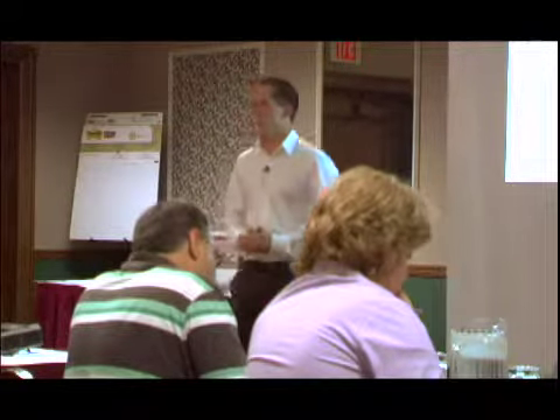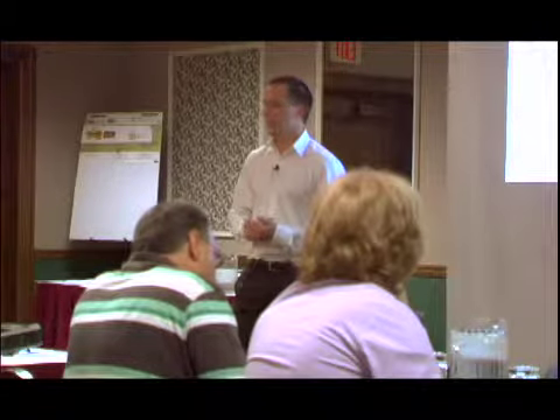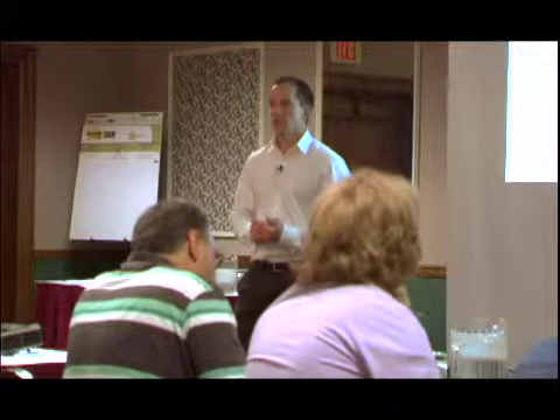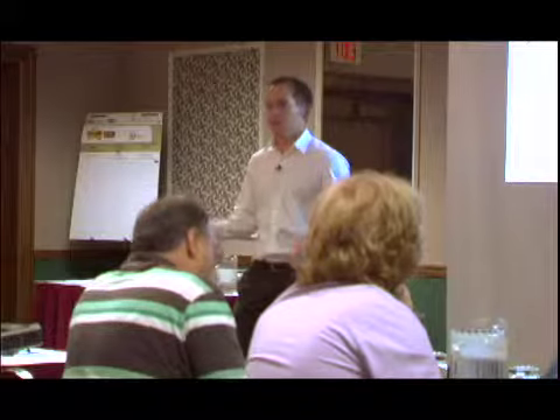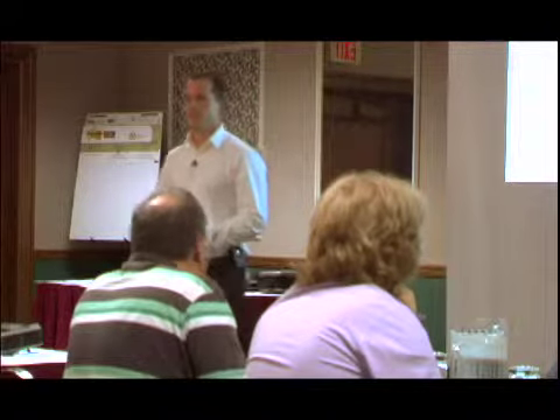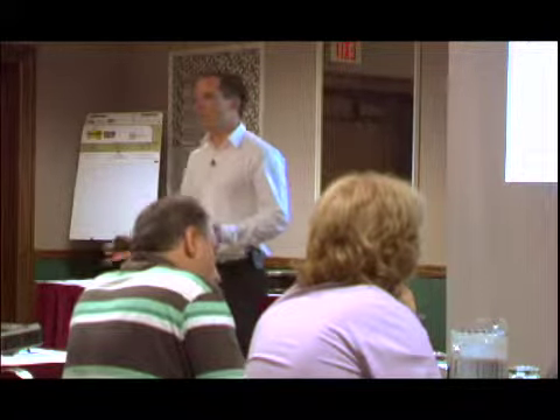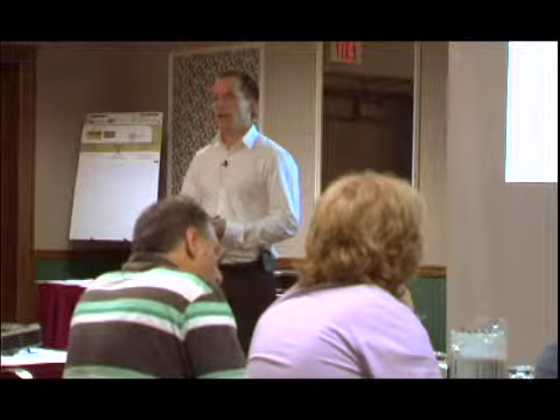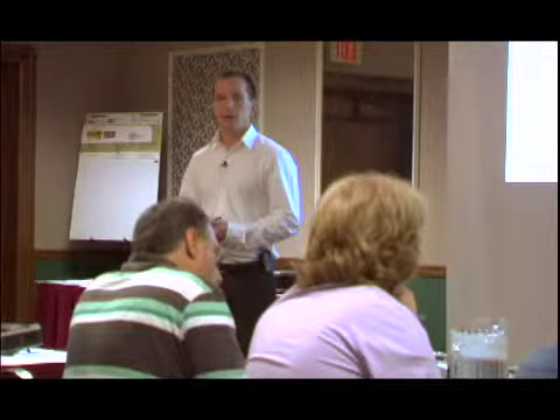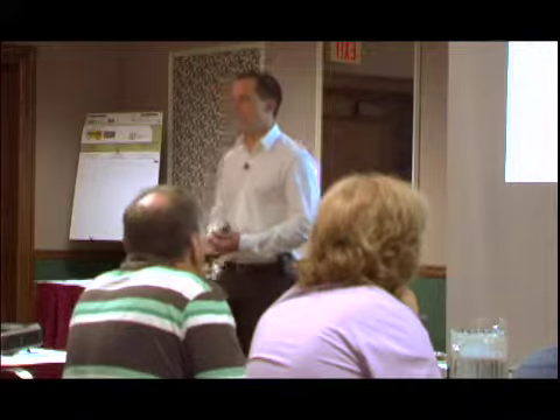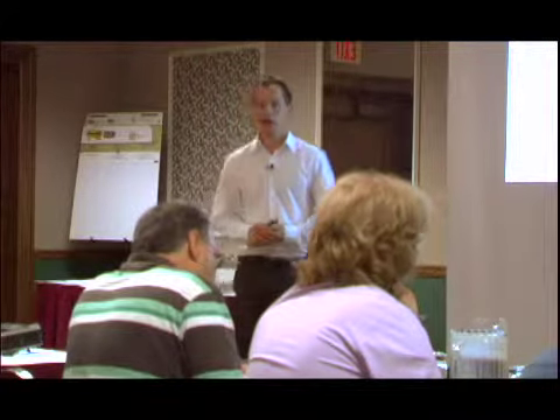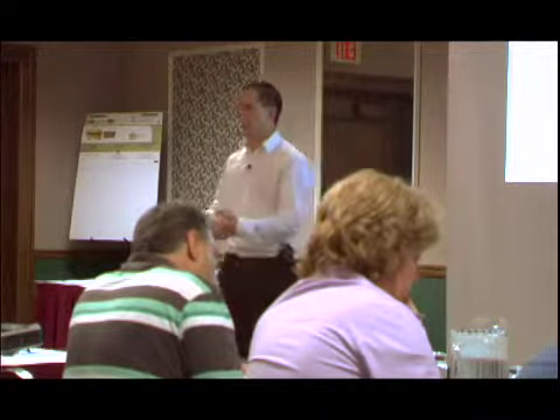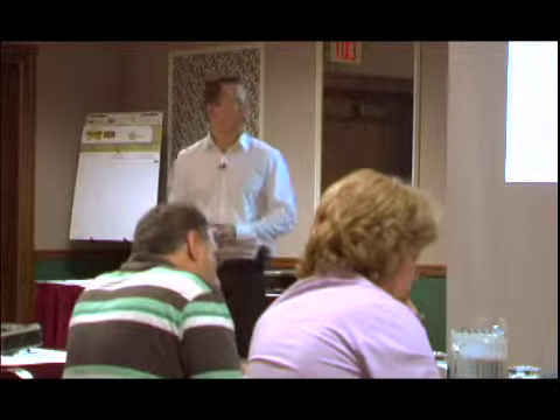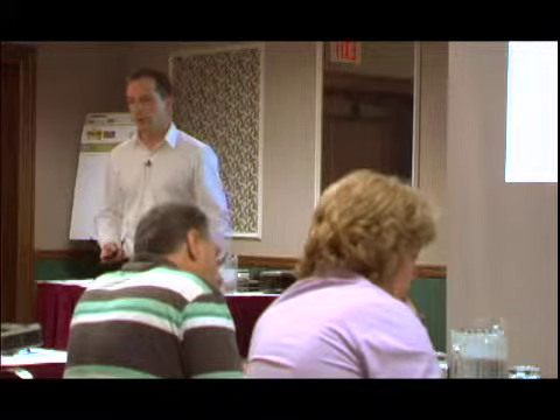Is anybody here struggling with NFPA 70E compliance for arc flash? Lockout-Tagout is referenced there—it's not a new regulation, they reference 1910.147. And what's the best way to prevent arc flash? Lock it out properly. If you shut it down and lock it out properly, you're not going to have an arc flash problem. Arc flash happens when something isn't done properly, or when something fails and an arc occurs while shutting down under a load.